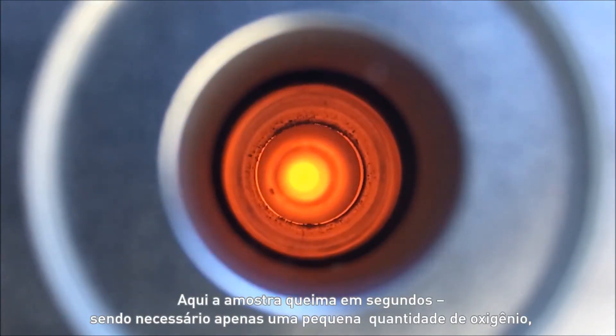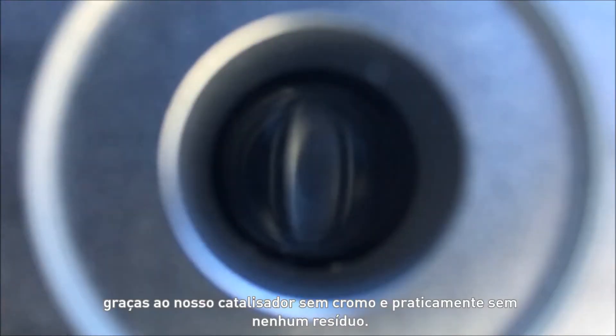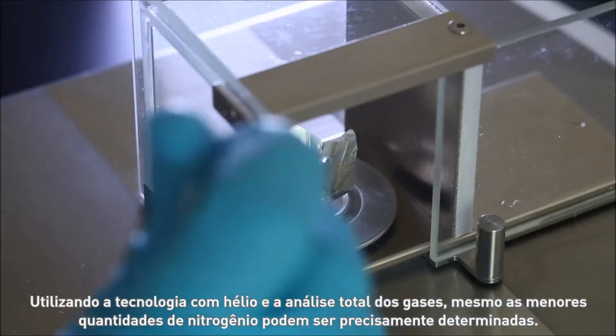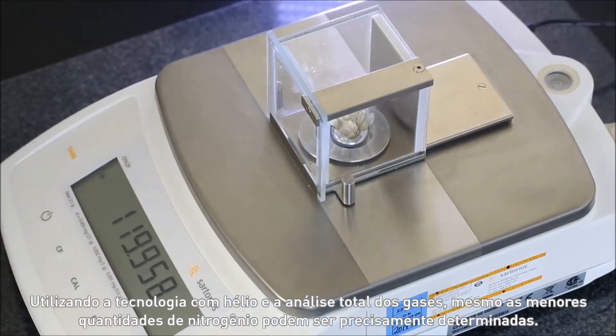DUMATHERM's core component is the high-temperature reactor. Here the sample combusts in seconds, with only a small amount of oxygen required, thanks to our chrome-free catalyst and leaving virtually no residue. Using helium technology and total gas analysis, even the smallest amounts of nitrogen can be precisely determined.